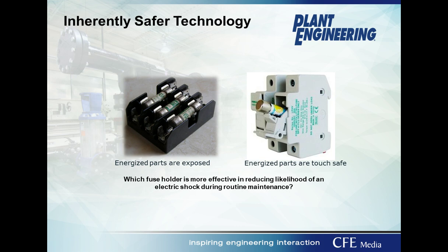Here's one more. This is comparing two different fuse blocks. These are 250-volt fuses. The fuse block on the left is a more traditional design. It's been around for a long time, very common. You can see the energized parts are fully exposed, the fuse ferrules, fuse clips are there. You have to be careful when you're working around this. Don't touch it, all right?